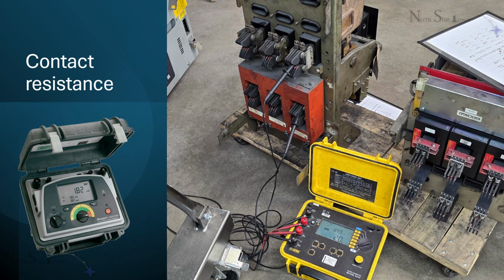We expect low, consistent values across all phases. Elevated or uneven results indicate worn surfaces, misalignment, bad adjustments, or contamination. This test verifies that contacts are properly seated, coatings are intact, and internal connections are tight. If problems are found, we can perform targeted maintenance like cleaning, retorquing, or rebuilding.